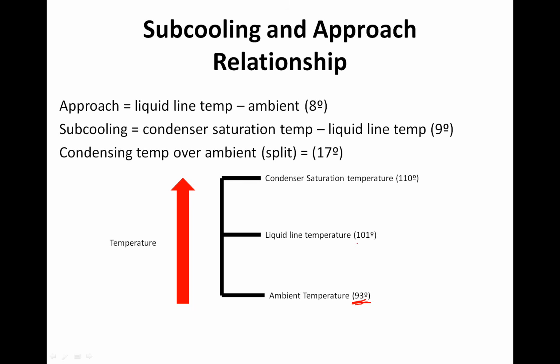But typically what we'll see is that the liquid line is always warmer than the outdoor air temperature, and the condenser saturation temperature is above your liquid line temperature. Okay? So when we talk about approach, you hear the term approach. Approach equals the liquid line temperature minus the ambient temperature. So in this case, if our liquid line temperature is 101 and our ambient temperature is 93, 101 minus 93, you have 8 degrees of approach.